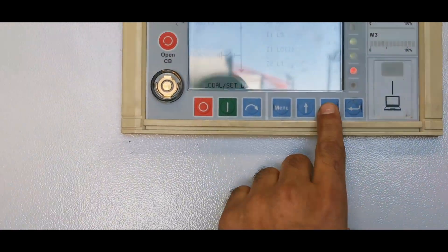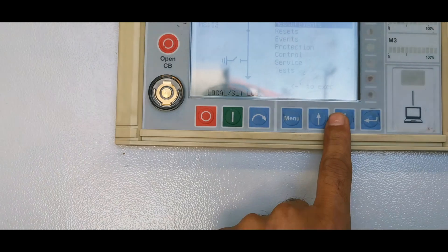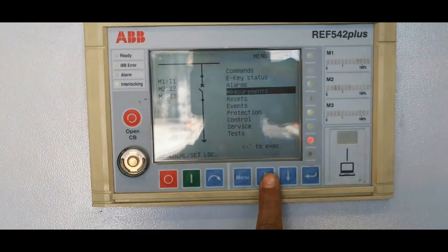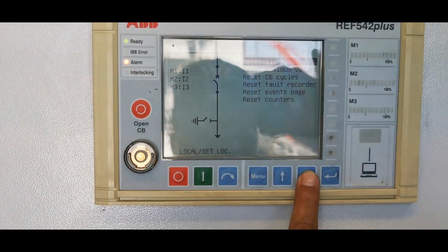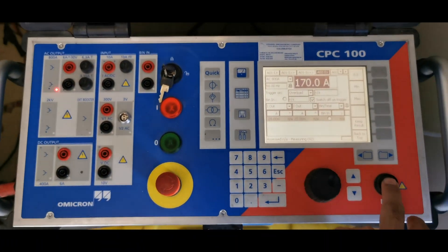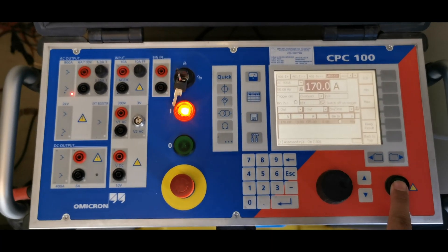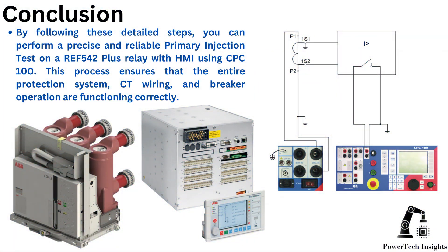Step 6: Resetting the system and repeating the test. Reset the REF542 Plus relay after a successful trip. Reset the circuit breaker manually or via HMI. Repeat the test with different current levels to validate performance. Adjust settings if the trip times or current levels do not match expectations.